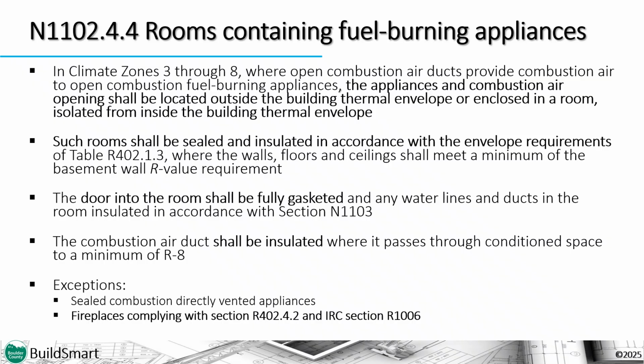I just bring this section of code up as it is an example that is still required even though it is not specifically listed on the N1106.2.1 mandatory requirements table when or if atmospherically vented appliances are installed that require bringing in combustion air. In essence, you will have to build an airtight and insulated room around the mechanical room that ensures that the building thermal envelope defines the atmospherically vented appliance that brings in combustion air as outside of the building thermal envelope.